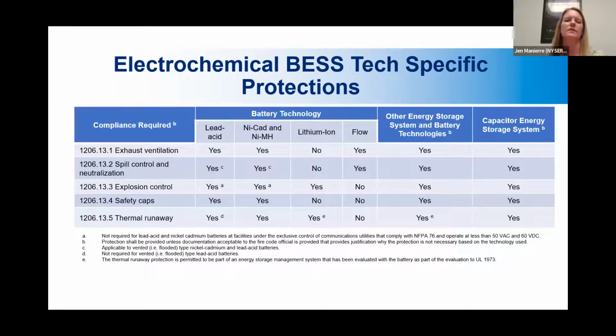So we like this. Another snapshot of the code and some of the different compliance requirements that apply based on technology type. So there's battery technology types across the top, labeling the columns, and the rows going across are showing what type of compliance is required based on that battery technology. I alluded to this a minute ago, but if you look at the first row here, exhaust ventilation, you'll see that yes, it's required for lead acid. Yes, it's required for nickel cadmium and nickel metal hydride, but it is not required for lithium ion.